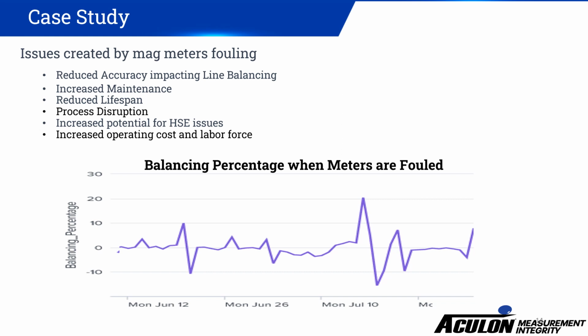You also see process disruption and increased downtime, increased potential for HSE issues such as H2S exposure, pinch points for fingers and hands, and handling heavy meters. You also see an increase in labor cost and workforce logistics. As you can see at the bottom, we have a balancing percentage for fouled meters. This is an example of when the meters were not treated and we were seeing balancing creep out between 10 and 20% over a 9 to 12 day time period.